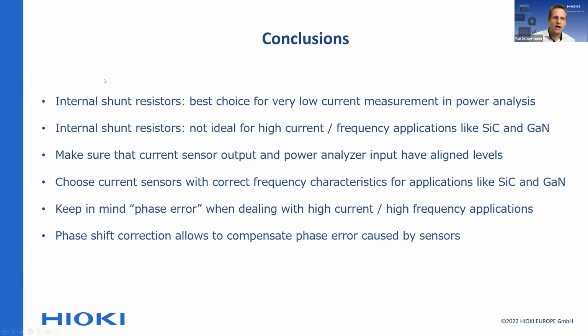So just summing that up, internal shunt resistors are the best choice for very low current measurement in power analysis. They are a very good and very sound and valid choice for low current measurements. That's why many Hioki current sensors use shunts as well. So shunts are not bad as such. The question is just, are they useful for higher currents and higher frequencies? And what I try to explain in these slides is that they're not ideal for high current and high frequency applications, simply because of the design of shunts, either with heat or with the high frequencies.